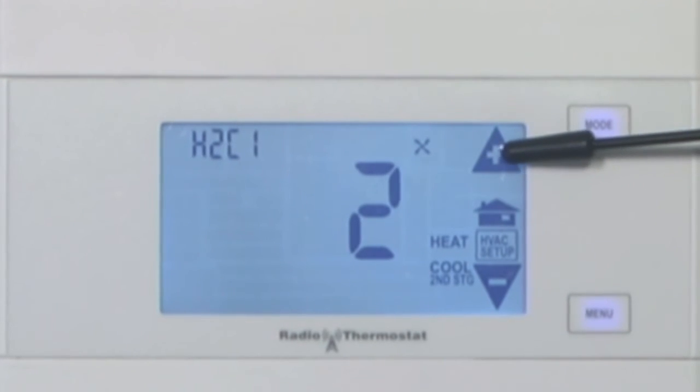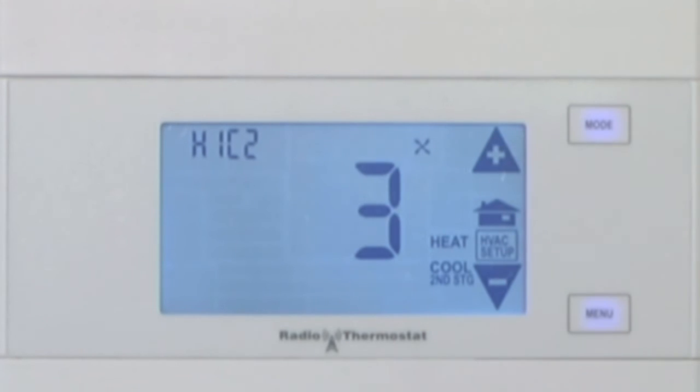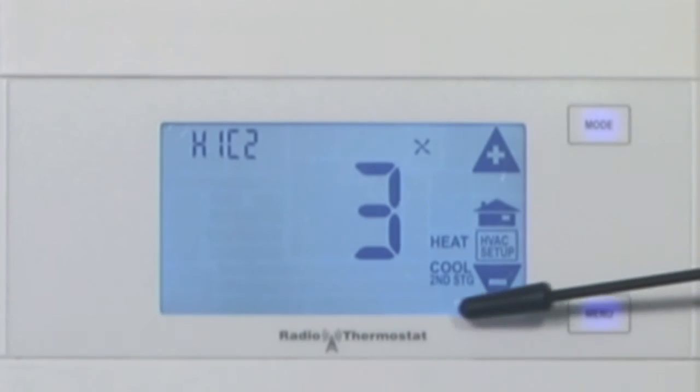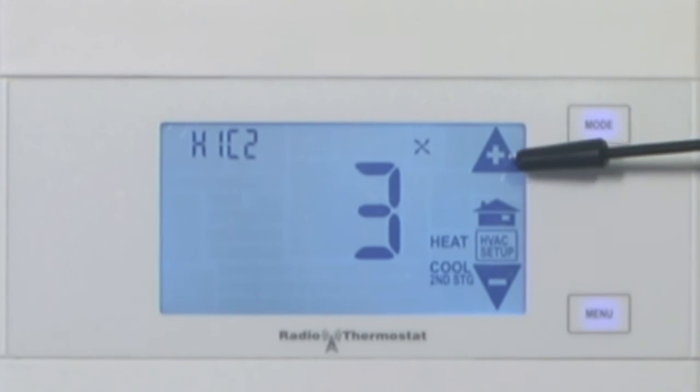Press it again and you go to one stage of heat, two stages of cool. That means your air conditioner has two stages, your heat has one. You can also look down at the bottom here, it says cool, second stage, heat, one stage.